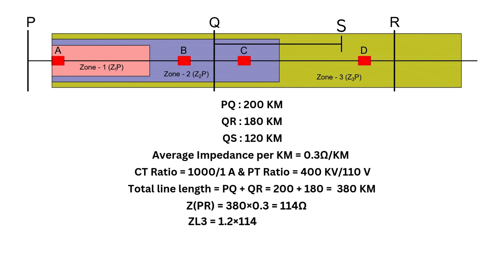Now, we set zone 3 to 120% of this impedance, 1.2 × 114, which is 136.8 ohms. Adjusting for the CT-PT ratio, 0.28 × 136.8 becomes 38.3 ohms. So, the zone 3 setting will be 38.3 ohms. And the time delay for zone 3 is 800 milliseconds.